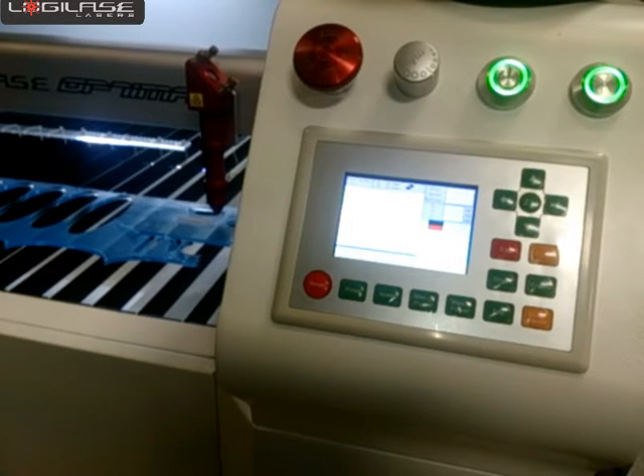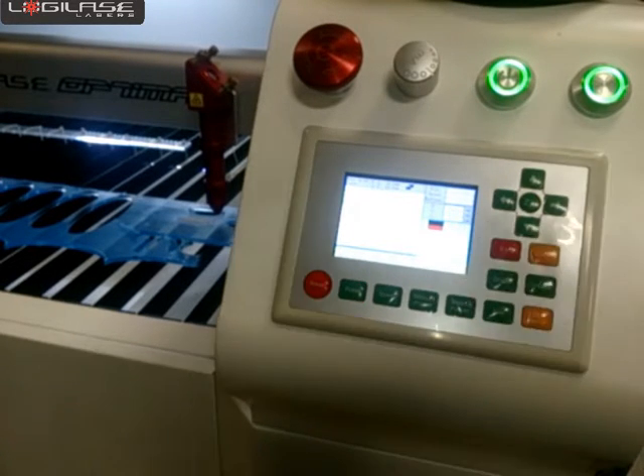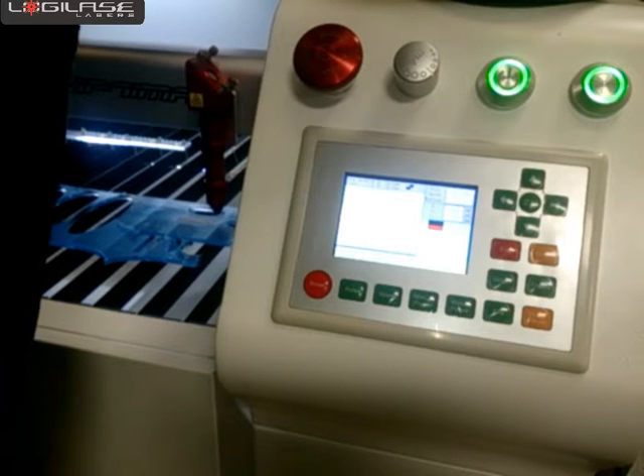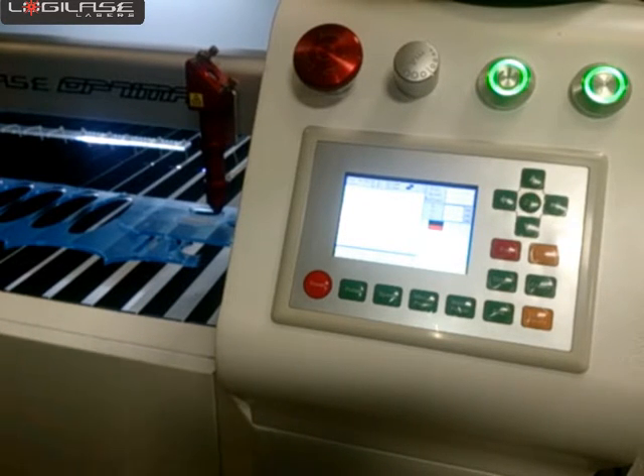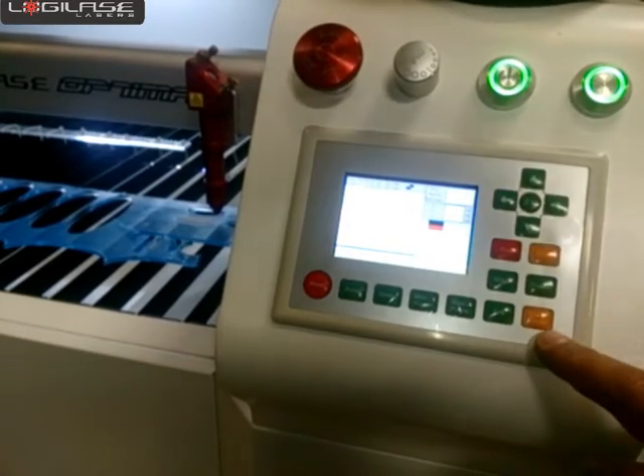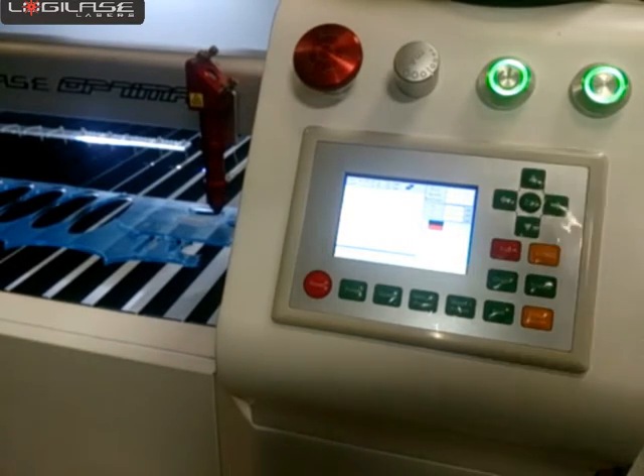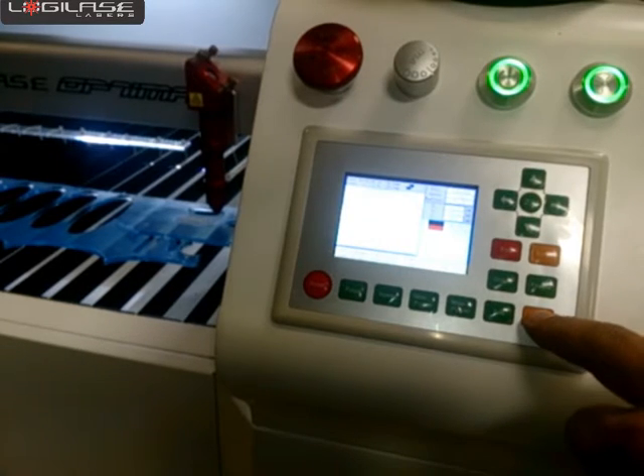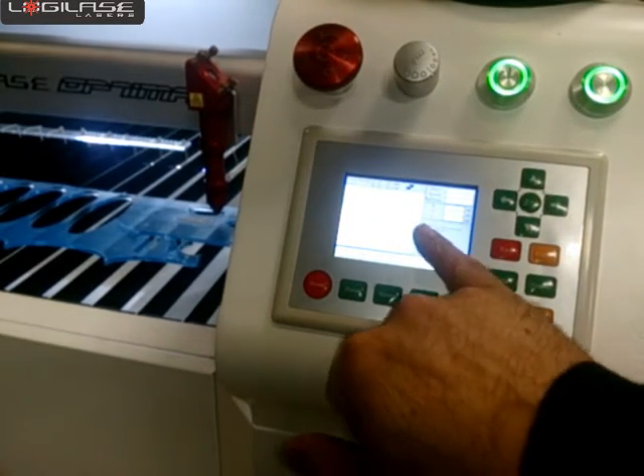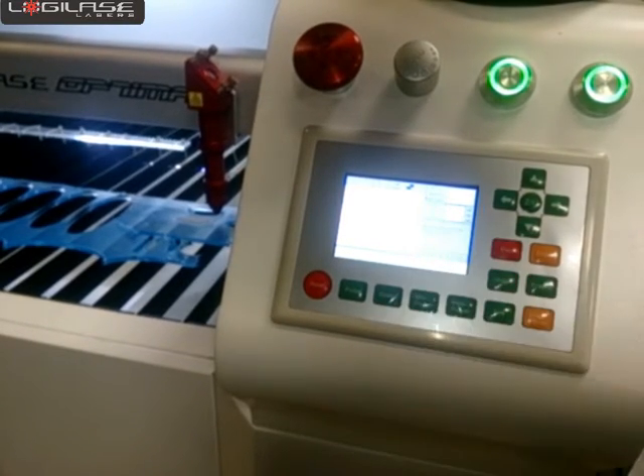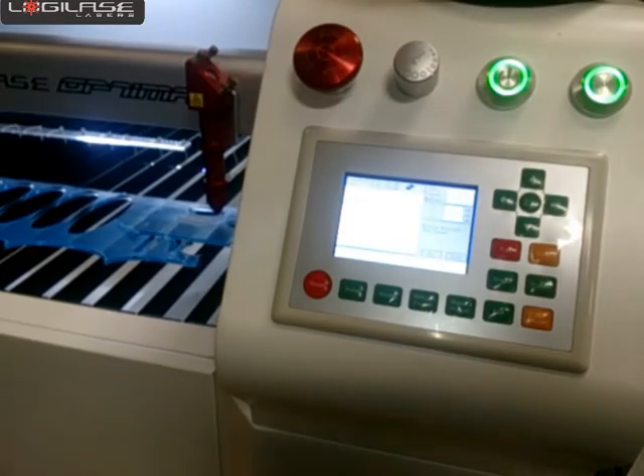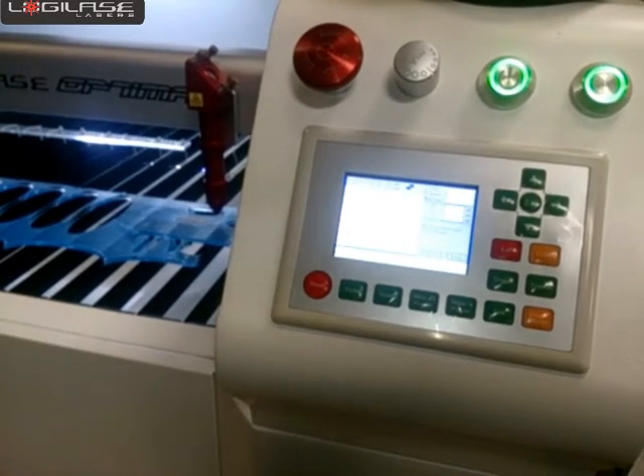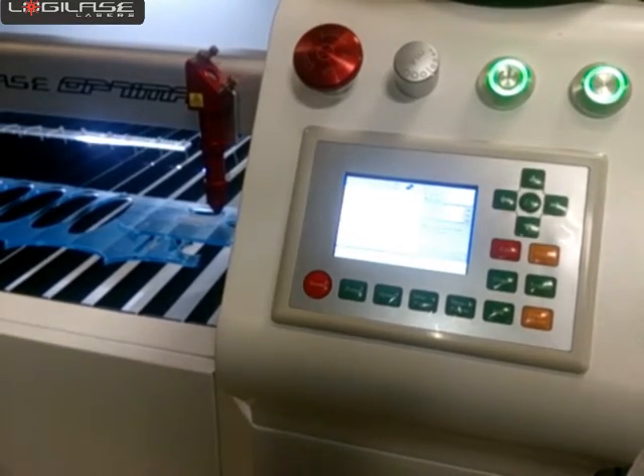But in a normal situation, if you don't close the door, the laser beam won't activate and it will give you the error. So we can show you how it looks when you don't close the laser machine door. We just remove the bypass for the switch, and let's just press start. It will show you machine protected, work paused. So that means the door is not closed, or it could also be caused when you don't have the water cooling unit on or connected properly. In both cases, you will receive the same message here.